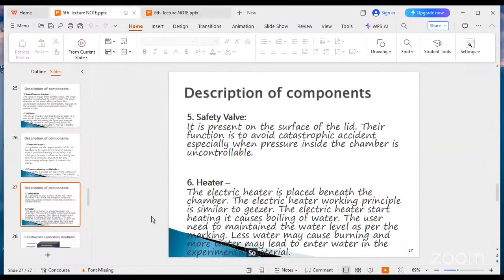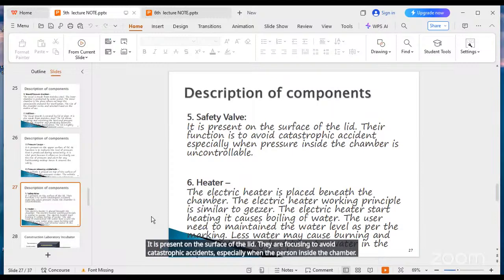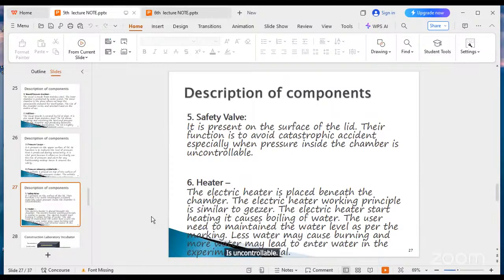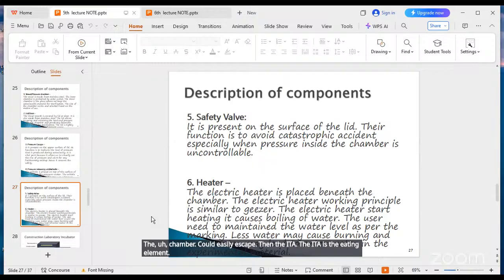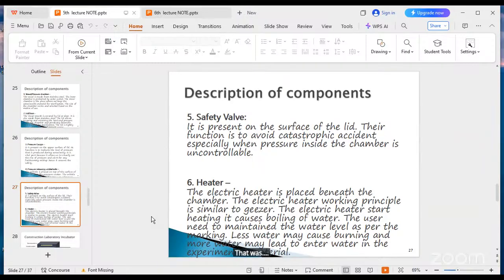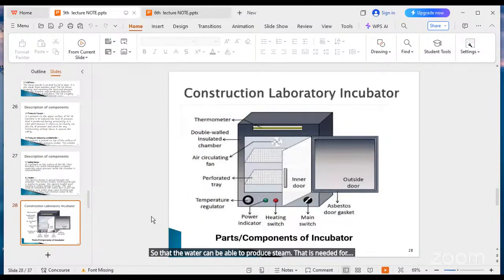So the next component we want to talk about is the safety valve. It is present on the surface of the lid. Its function is to avoid catastrophic accidents, especially when the pressure inside the chamber is uncontrollable. You can manually press it so that the pressure inside the chamber can easily escape. Then the heater. The heater is the heating element that boils the water inside the boiler so that the water can produce the steam that is needed for the sterilization process.